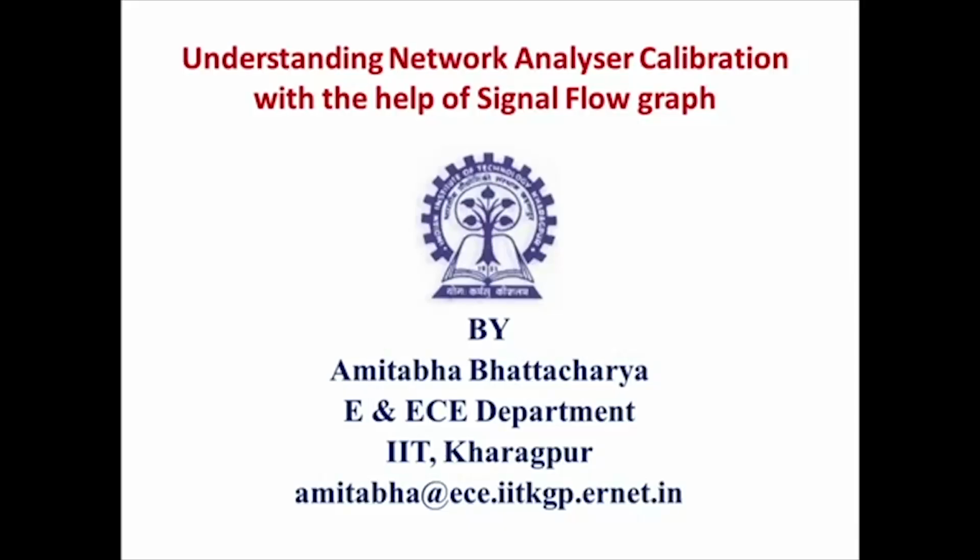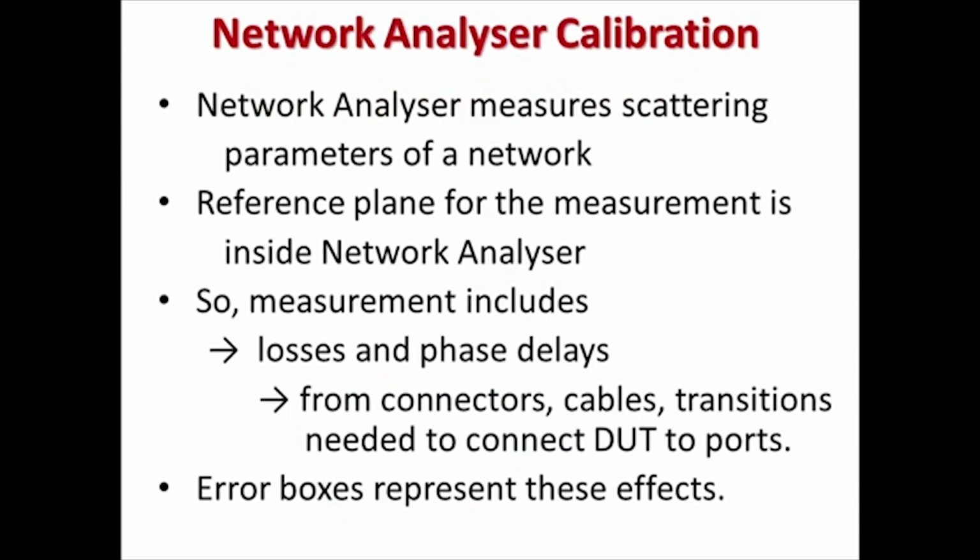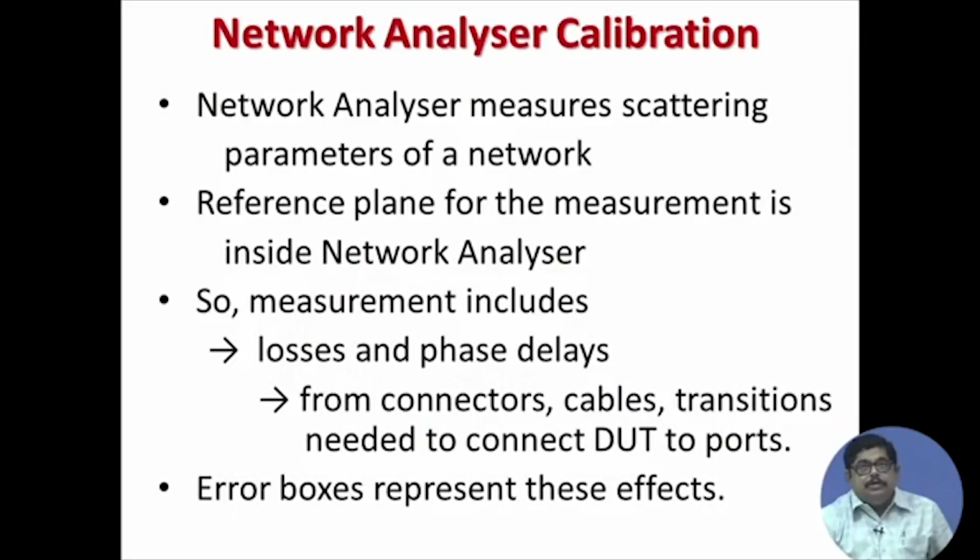Welcome to this lecture, 19th lecture, where we will see network analyzer calibration with the help of signal flow graph. Now, network analyzer we have introduced in this course, that it measures scattering parameters of a network. That is why it is a very important instrument in measurements.